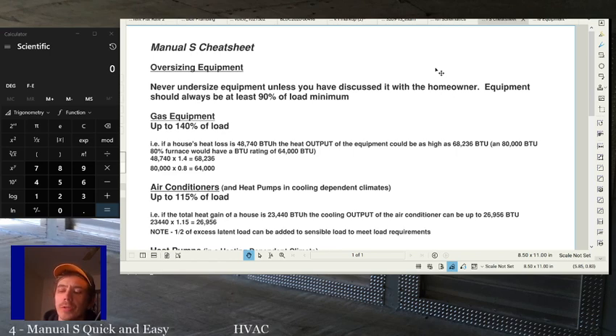So if you undersize equipment on a 95-degree day, you may only be able to get the house to 76. Odds are, you're still going to be able to maintain close to that, but on a 100-degree day, for instance, you might only be able to get the house to 77, 78, maybe 80, right? That's another good thing to keep in mind. Once you hit 95 degrees outside, that equipment should essentially be running all day. So a common complaint you get on a very hot day is my equipment's running all the time and it's not cool in the house.